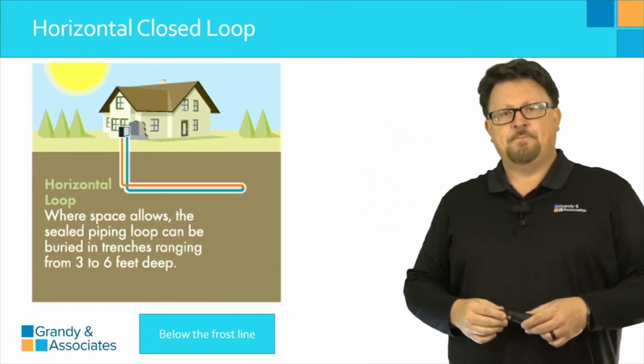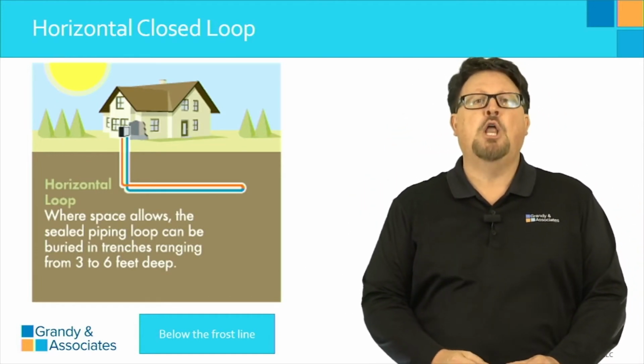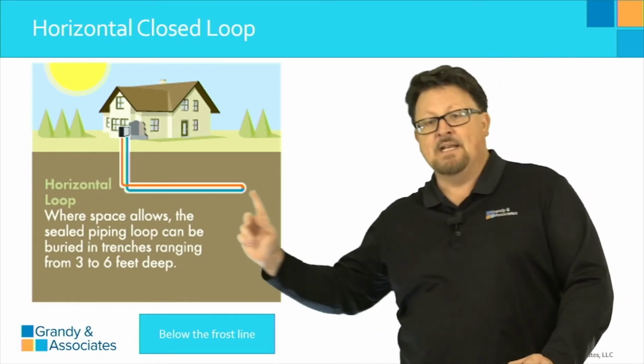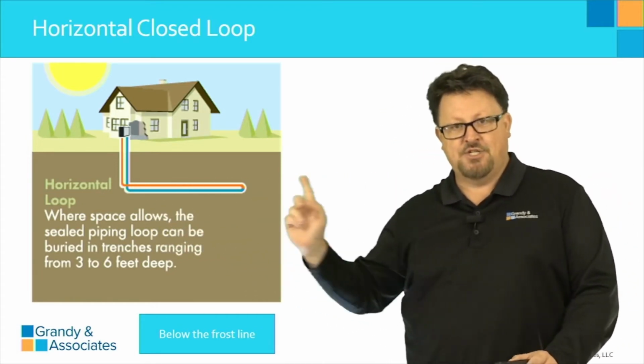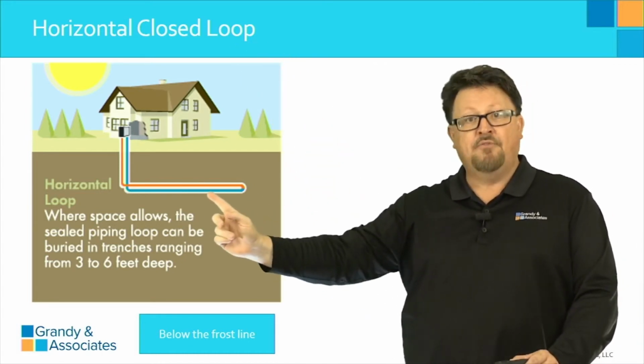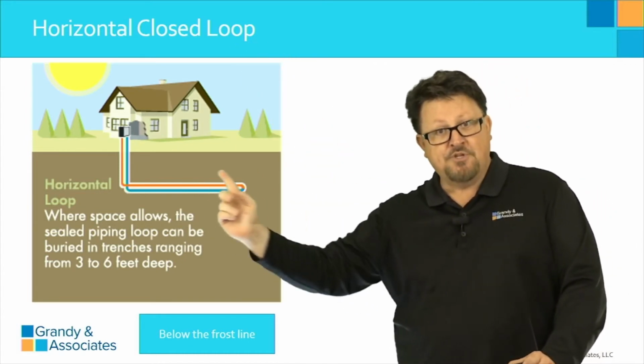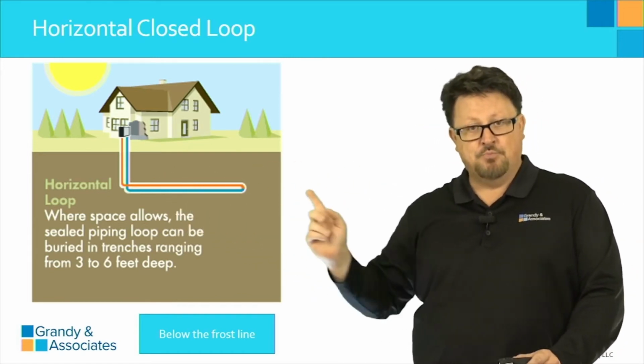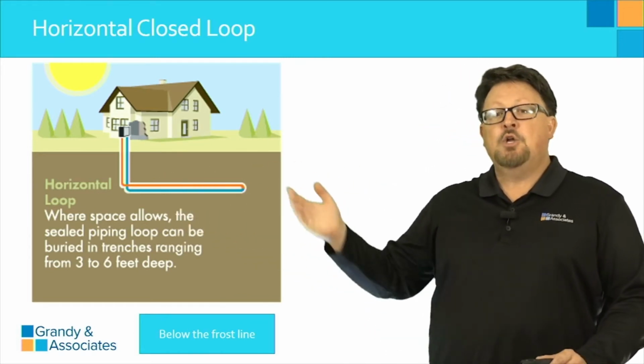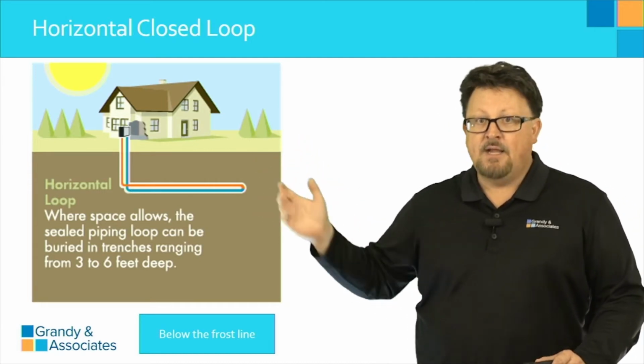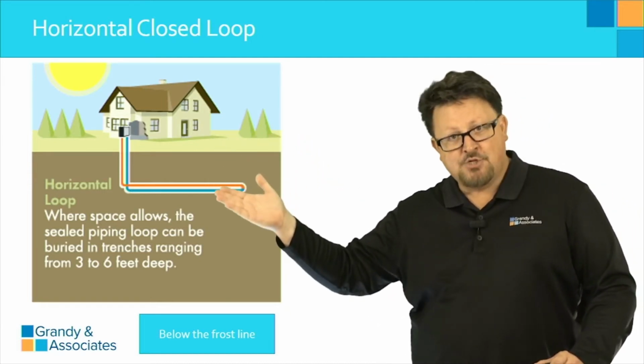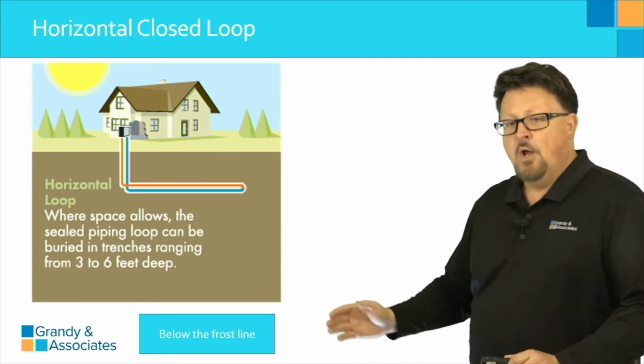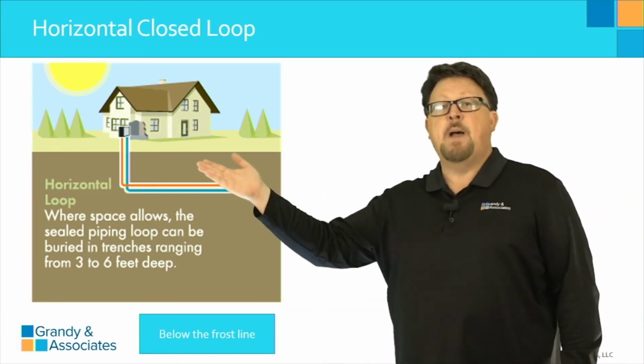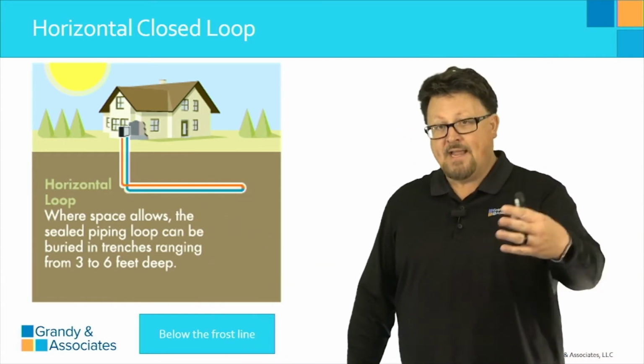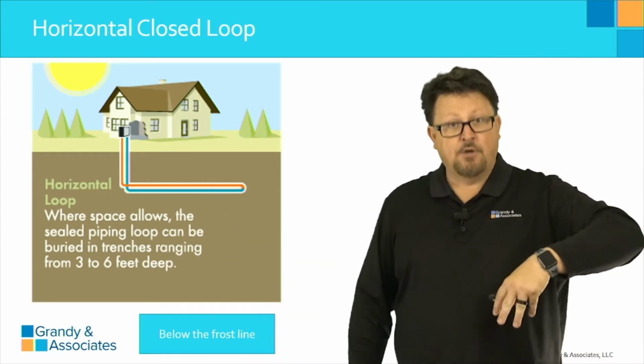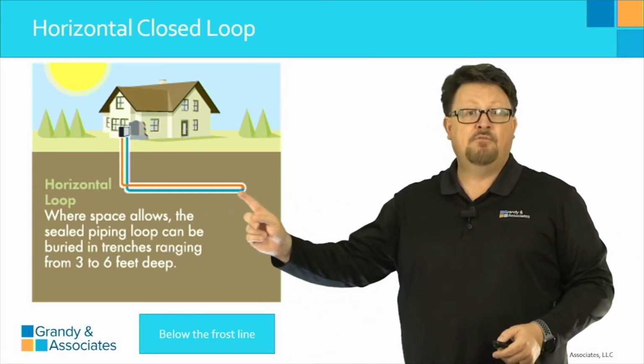Let's look at these loops. The first is the horizontal closed loop — horizontal because it's installed horizontally, closed because we're not pulling from a live water source, just recirculating water in the loop. The biggest thing to remember: always look before you dig, checking for electric lines, plumbing, and making sure the pathway is clear. You also need to install the horizontal loop below the frost line, which can vary depending on your market.